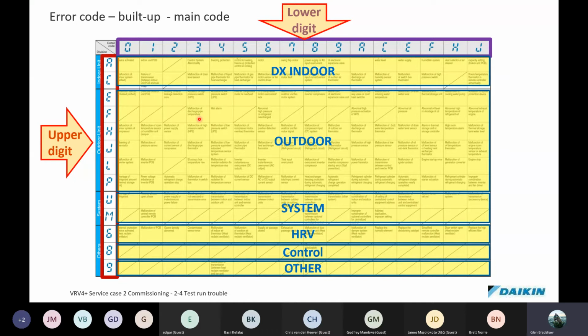All right, so the type of thing, we've got a high discharge temperature with F3. This could be from a shortage of refrigerant. Okay, with high discharge superheat. Remember, we spoke about it just now. That type of thing, we're going to see if we're not getting enough suction cooling back on the compressor. All right, so just always think about that. When you see error codes, don't think in terms of parts replacement only. Think in terms of actually resolving an abnormal operation of the system.